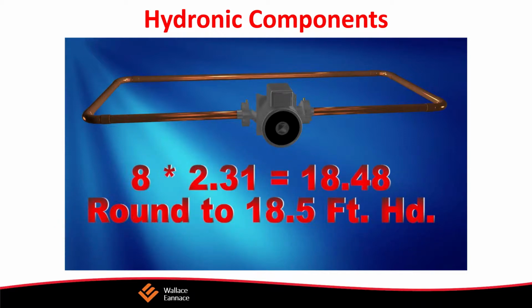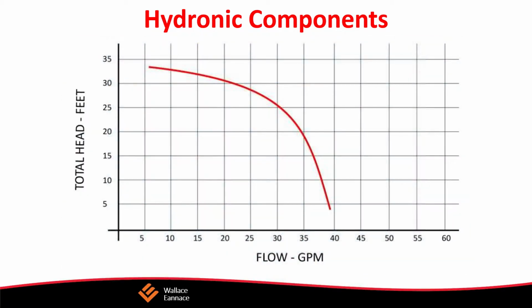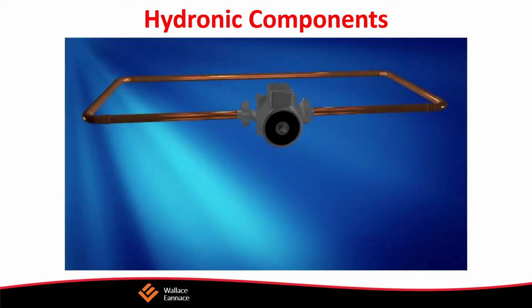Have you ever wondered how a circulator moves water in a system? Today we're going to cover these topics and more. These devices are actually very simple when you break them down. They are made up of separate parts. The volute is the body of the circulator. It is where the water enters and leaves the circulator and is the home of the impeller. The impeller is the part of the circulator that spins, slinging water away and creating the delta P, or difference in pressure, when the motor is energized.